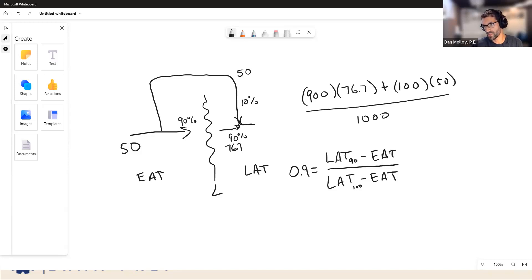And so if we know this enters at 50 and we know that it could leave at 76.6 and we know the coil efficiency is 90%, the only thing we don't know is the leaving air temperature. And it turns out that the leaving air temperature that comes out of this calculation is exactly the same as what you would get if you do this mixing calculation. So your understanding is absolutely correct.